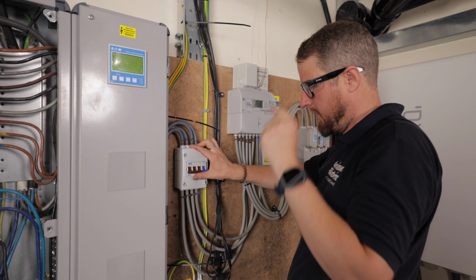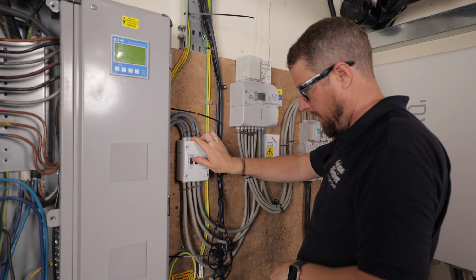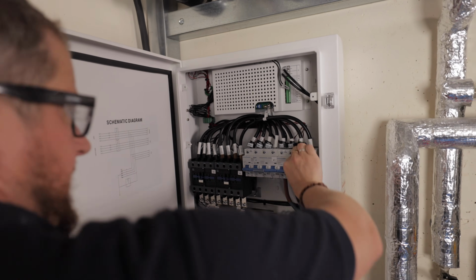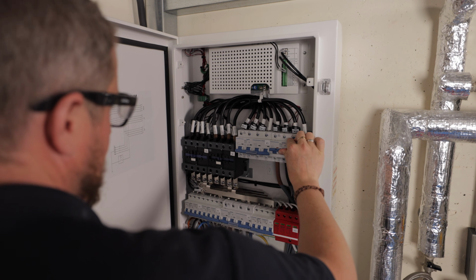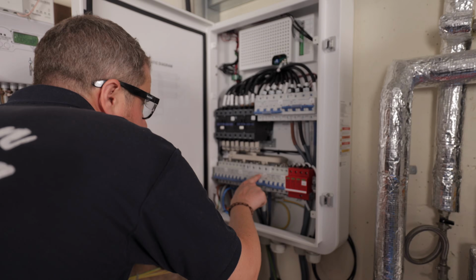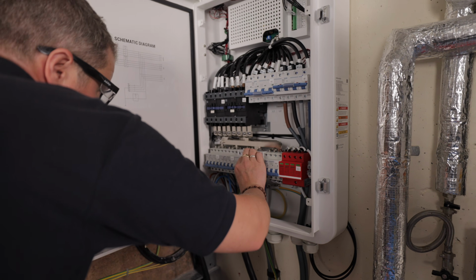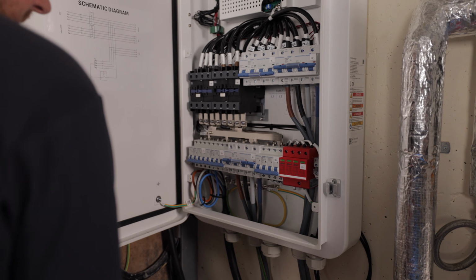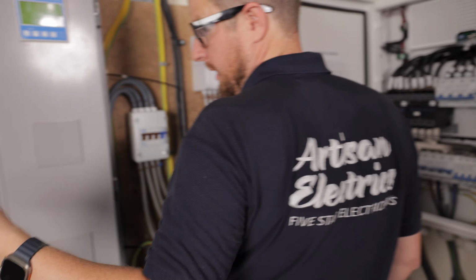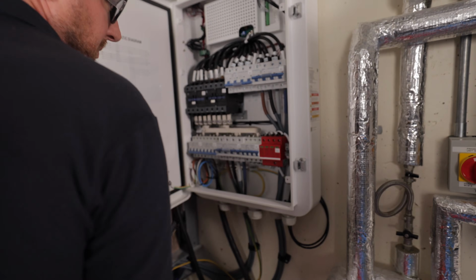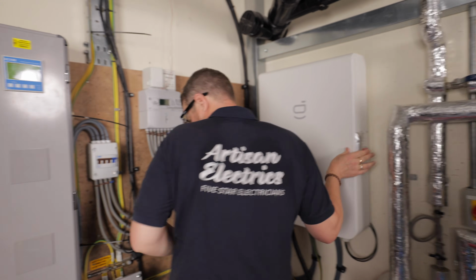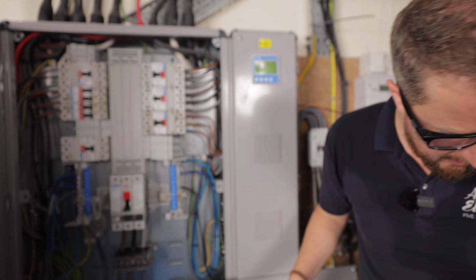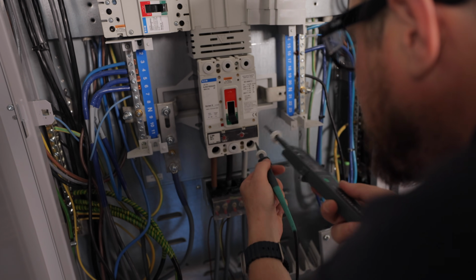Right, moment of truth. So power on to our gateway. So this is our grid breaker. Boom, contactor kicks in. Power our outgoing. Turn this on. That will then send power to our main panel. We should also turn the circuit surge protector on. And now we can do a polarity test here. There we go. Yeah, that's all good.